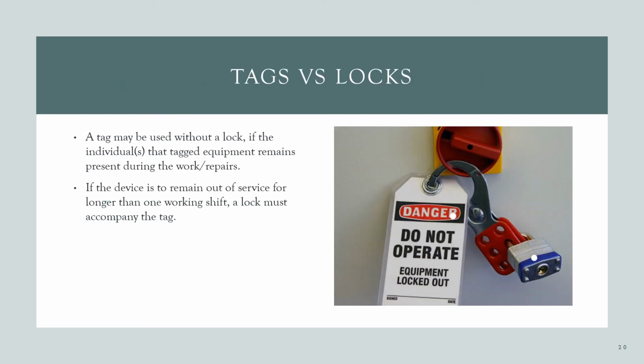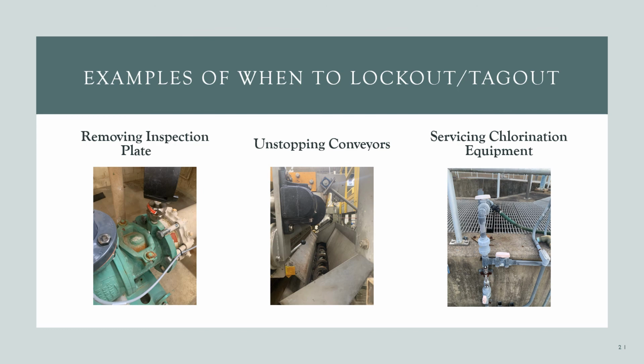So when do you use a tag versus when do you use a lock? You can use a tag without a lock if the person tagging it out stays there with the equipment and is present during the work and repairs. If the device is to remain out of service longer than one shift, a lock must accompany the tag. And here's some examples of when to lock out, tag out. The inspection plate on a pump being removed for a clog. You don't want that pump coming on when you're elbow deep in there.